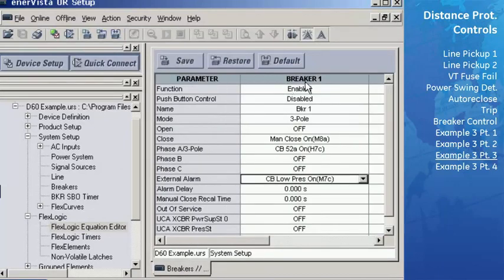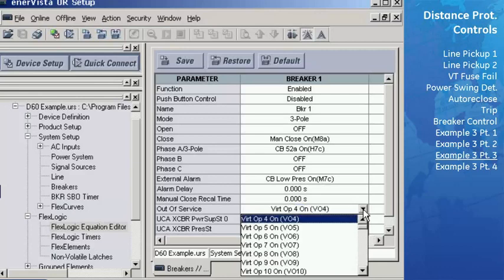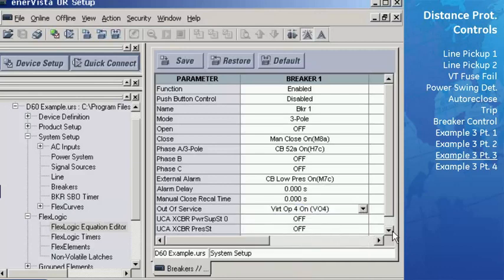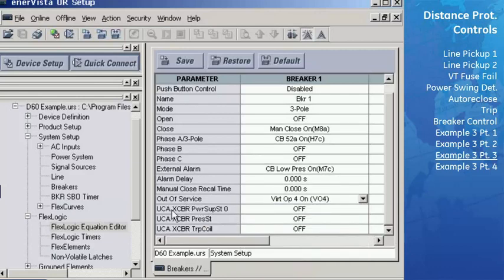Go back to the breaker control menu, then set Out of Service to Virtual Output 4 on. The other settings are for detailed applications using UCA communications protocol and won't be used. Save these settings to the settings file and close this window.